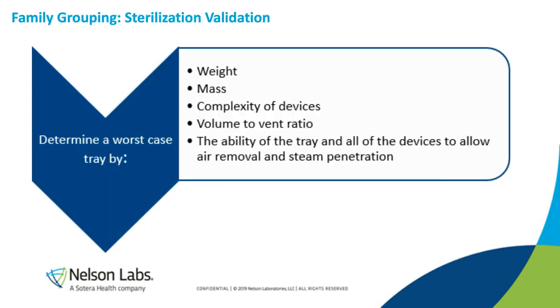Now we look at different things when we look at family grouping for sterilization validations. We need to determine a worst case tray by looking at the whole weight of the tray, the mass of the tray, including the mass of each device, the complexity of each device, the volume to vent ratio, and the ability of the tray and all the devices to allow appropriate air removal and steam penetration.